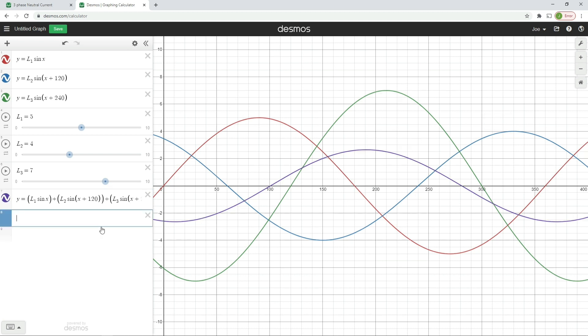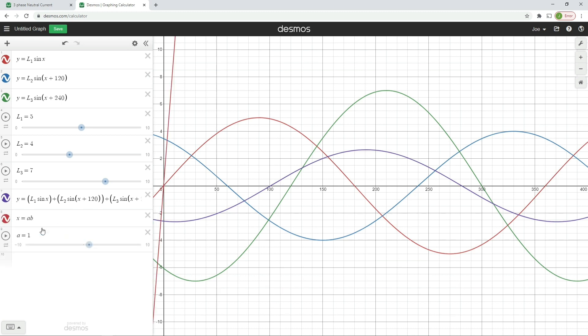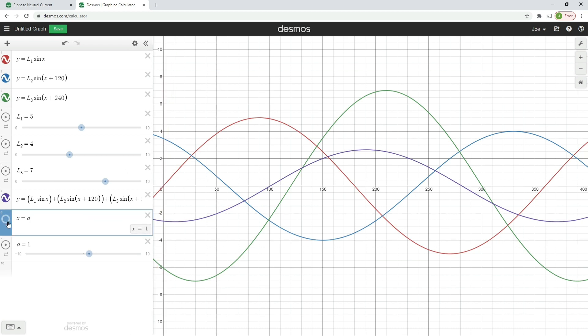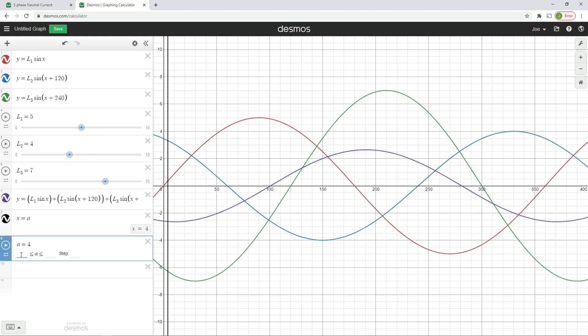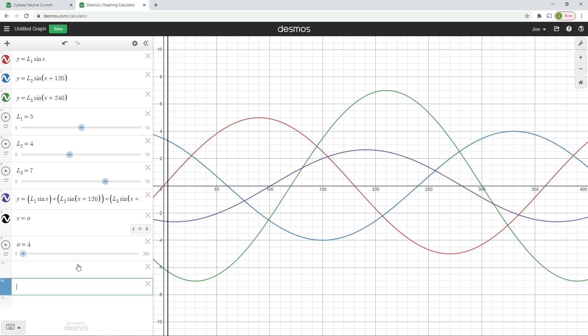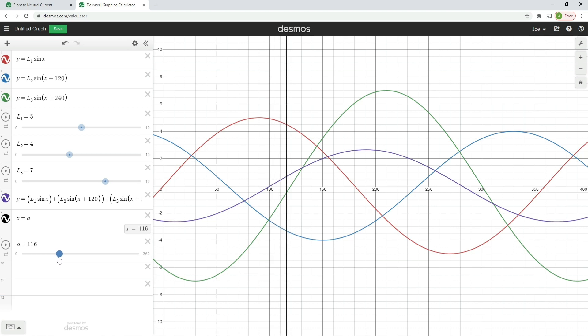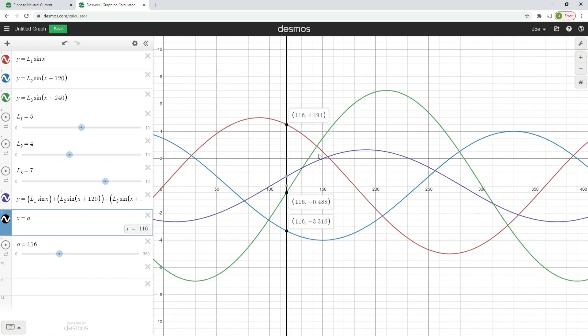Let me demonstrate this further by adding a vertical line. I'll use x equals A with a slider, color it black so it stands out, and set the range from zero to 360 so I can place it anywhere. If I pop it at a particular position, you can see three points on the L1, L2 and L3 waveforms. Taking the y values — 4.494, minus 0.488 and minus 3.316 — and combining them gives 0.69, which matches the purple neutral waveform at that point. The software does this at millions of points along the graph.